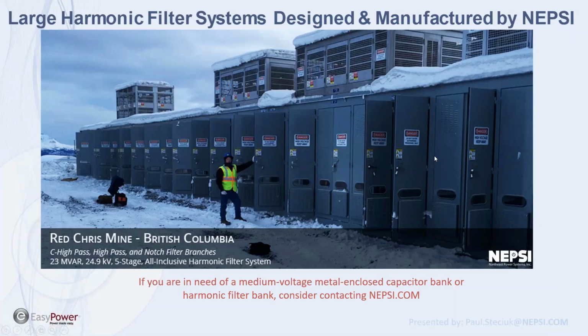NEPSI is a manufacturer of metal-enclosed harmonic filter banks and capacitor banks. We actually build this equipment here. We build this enclosure, and we populate the enclosure with the L, R, and C parameters that come out of your harmonic studies. Typically, harmonic studies are about determining the performance of a harmonic filter, choosing the LRC parameters, the type of filter, the tuning point, and the kVAR, but they very seldom get into the details of what it takes to design and build a harmonic filter. That's what NEPSI does. There's a few of us out there that do this.